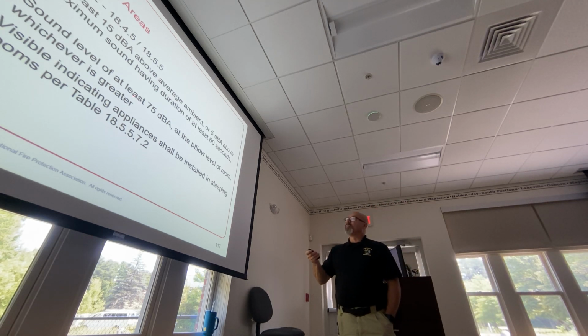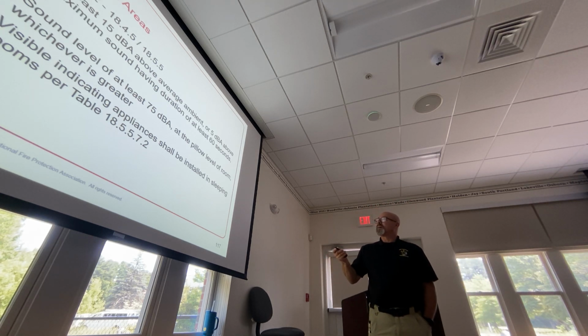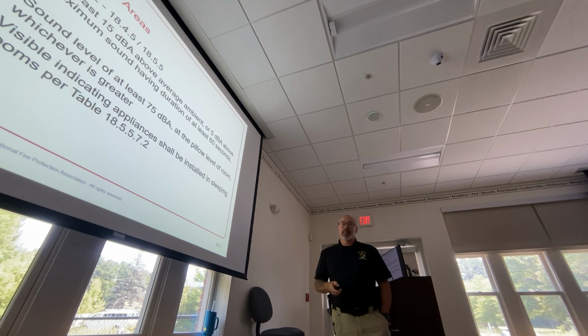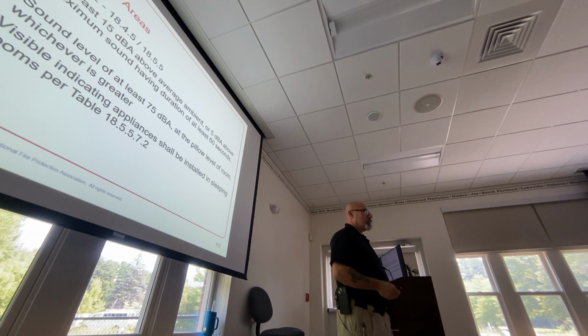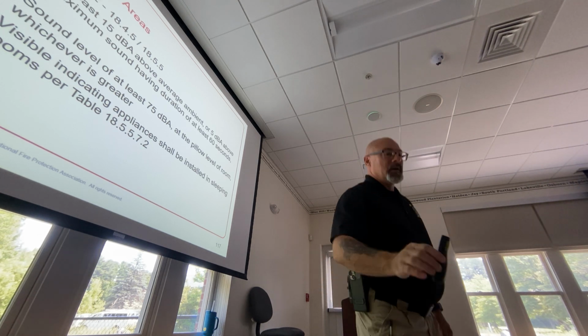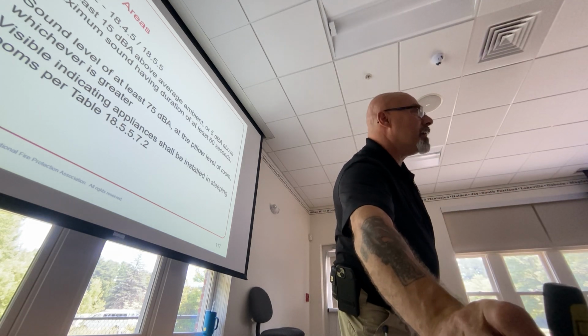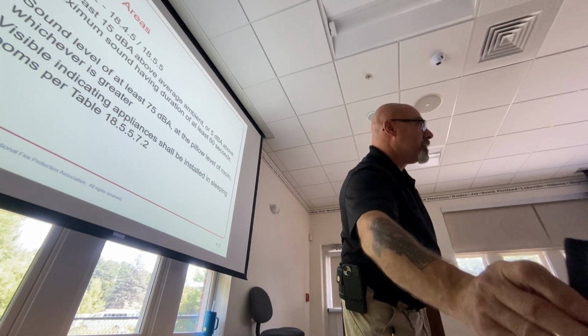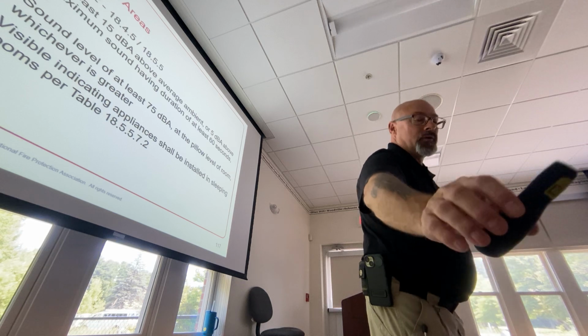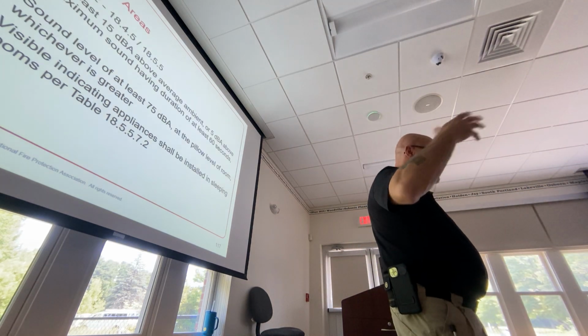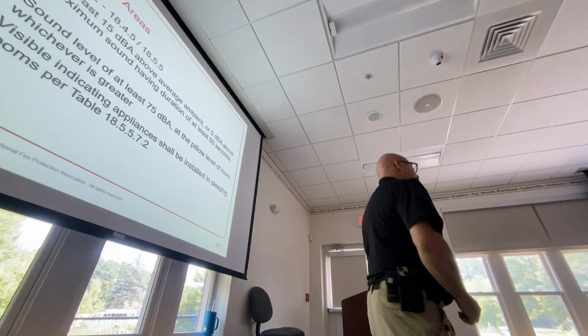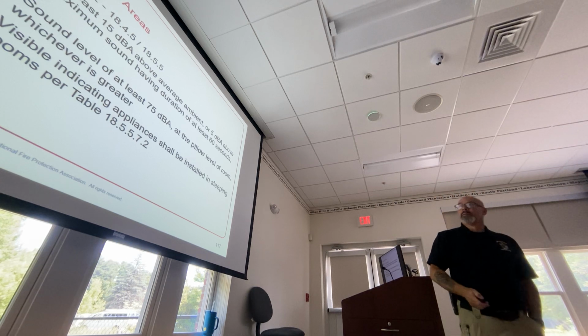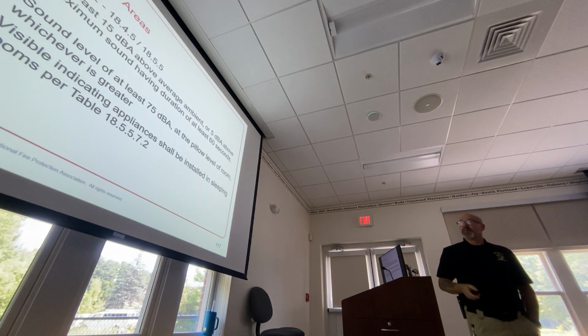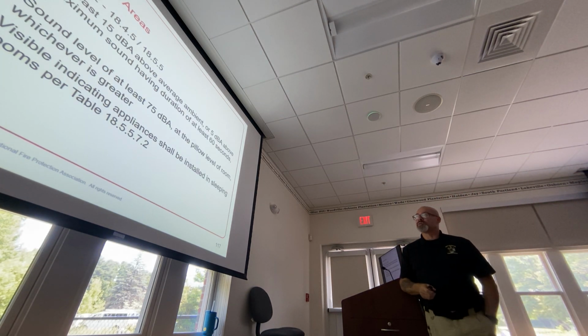So the sound level of at least 75 decibels at the pillow level of the room. So you're actually going to take your meter where you would lay your head on the pillow. That's what the pillow level means. So you put your sound meter there and sound the alarm to test it. It has to be at least 75 decibels at that location.